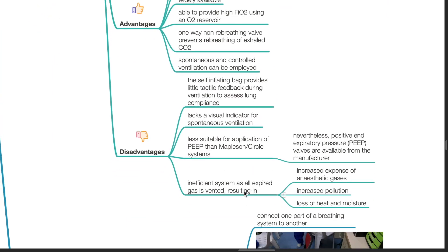Disadvantages. The self-inflating bag provides little tactile feedback during ventilation to assess lung compliance. It lacks a visual indicator for spontaneous ventilation. It is less suitable for application of PEEP compared to the Mapleson and Circle systems. It is an inefficient system as all expired gases are vented, resulting in increased expenses of anesthetic gases, increased pollution and loss of heat and moisture.